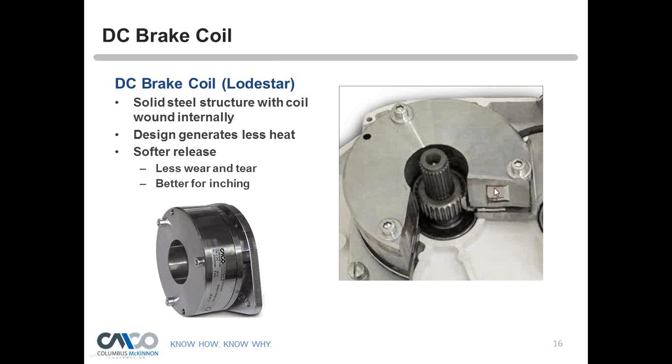You can see the brake coil, which in this case is not removable from the brake. But this is the brake coil. And again, there's our steel structure. Okay, and our brake gap, you can see, is right here.